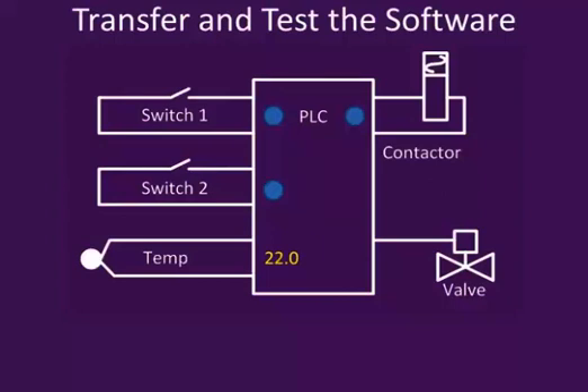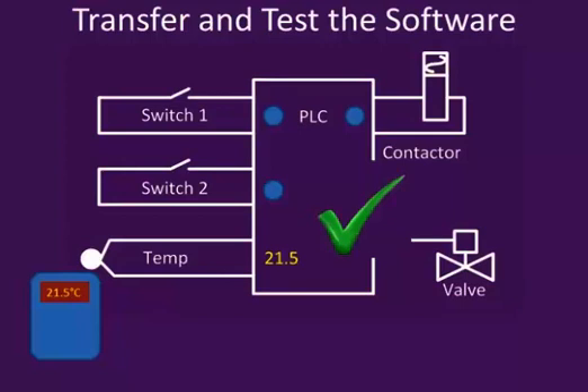We may also need to calibrate sensors. In this case, we'll calibrate the temperature sensor. So we get our test gauge, and our test gauge says 21.5. And in the software it says 22, so we need to calibrate that. There's probably an offset value that can be entered to make the PLC match the calibrated test instrument. And then once that's done, it's all good. 21.5, 21.5.